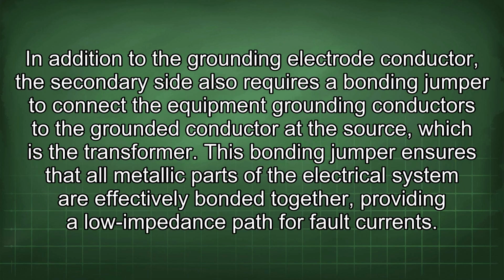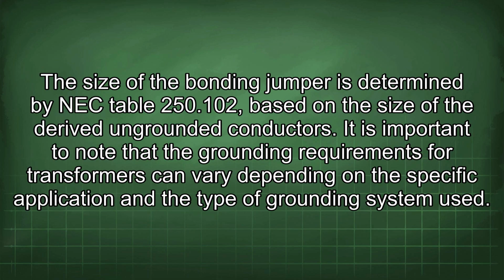In addition to the grounding electrode conductor, the secondary side also requires a bonding jumper to connect the equipment grounding conductors to the grounded conductor at the source, which is the transformer. This bonding jumper ensures that all metallic parts of the electrical system are effectively bonded together, providing a low impedance path for fault currents. The size of the bonding jumper is determined by NEC Table 250.102, based on the size of the derived ungrounded conductors.